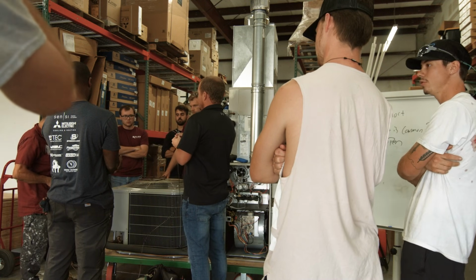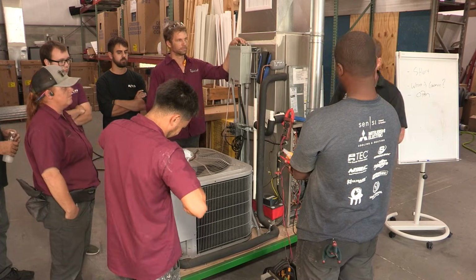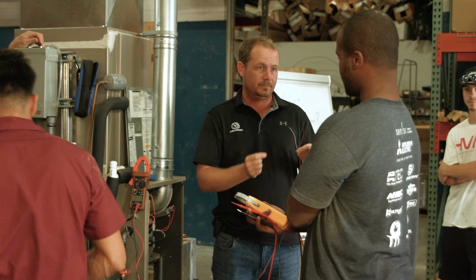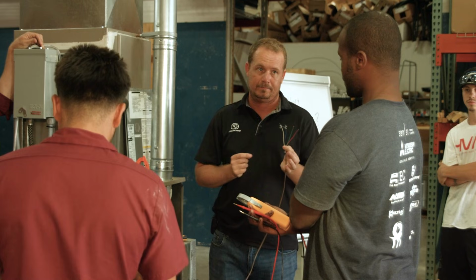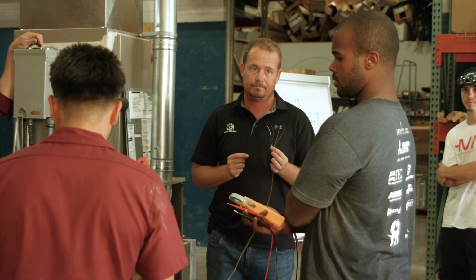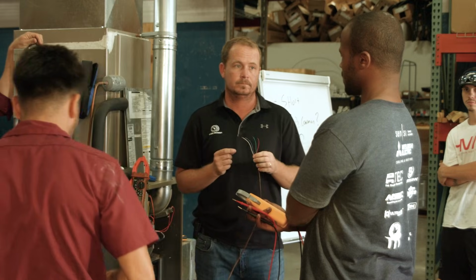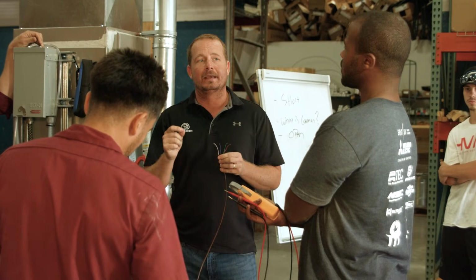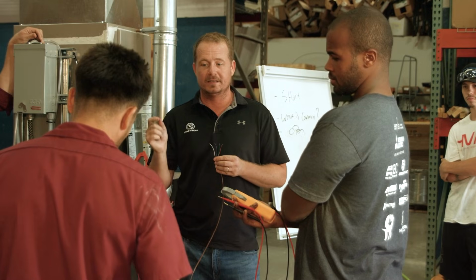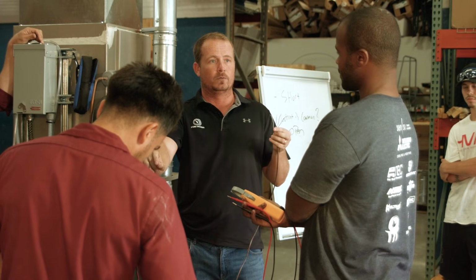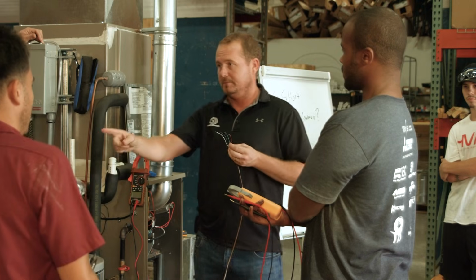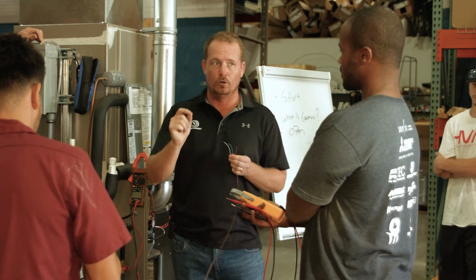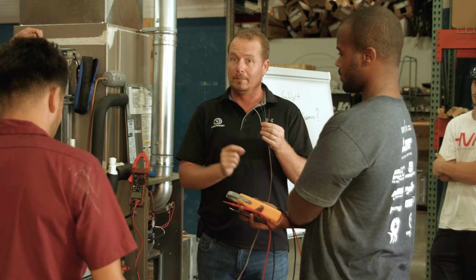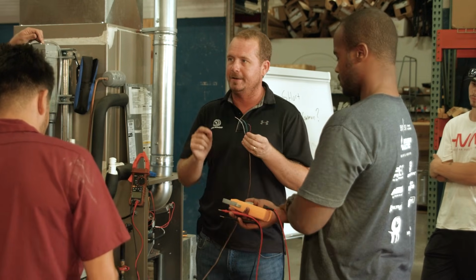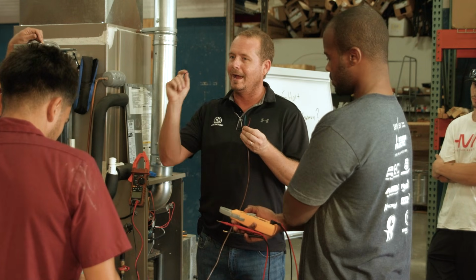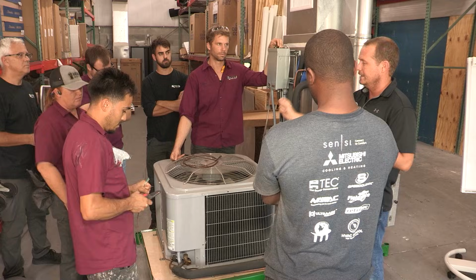Now, if I want to confirm there's no break in these wires between here and there, how would I do that? You could test it to ground, if you were checking for a short. But the key thing is: if there's a break in one of these wires, what is that called? It's called an open. So I'm checking for an open, looking for a break, looking to find where there's no path where I'd expect there to be one. This is a common test.